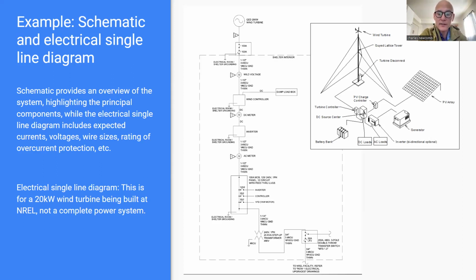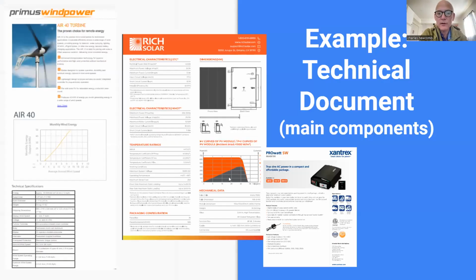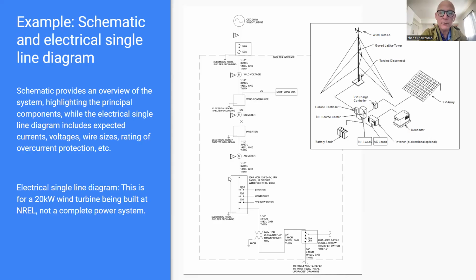Versus the single line, which is kind of fun. It's for a 20 kilowatt turbine we just put in for NREL for Ian this fall, and we're waiting for an inverter upgrade. What we wanted to show you is that we're putting some overcurrent protection in there, showing what size the overcurrent is, and showing you the conductor size.